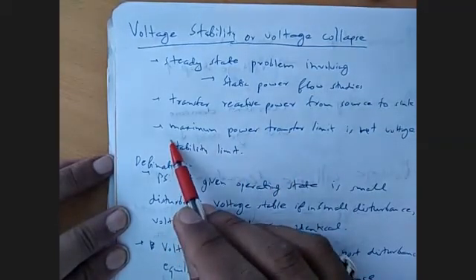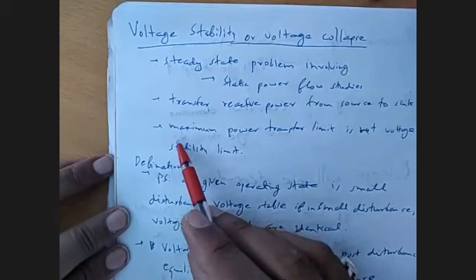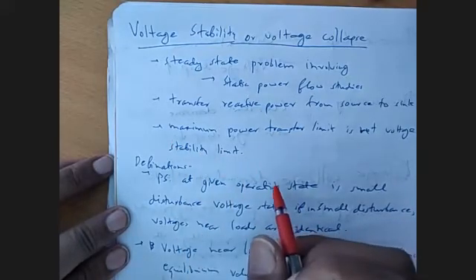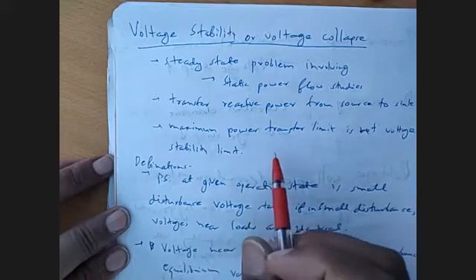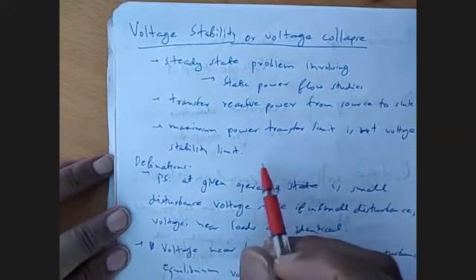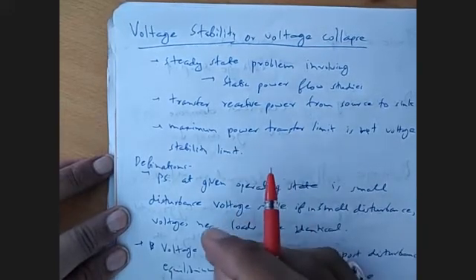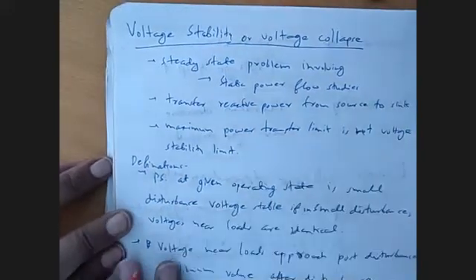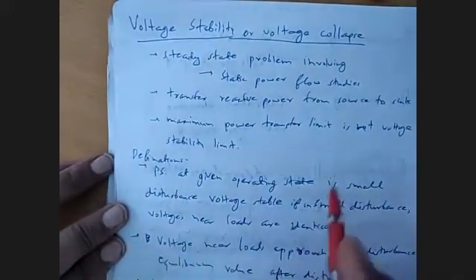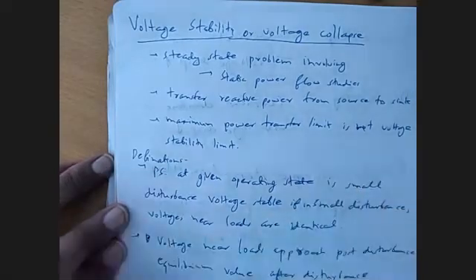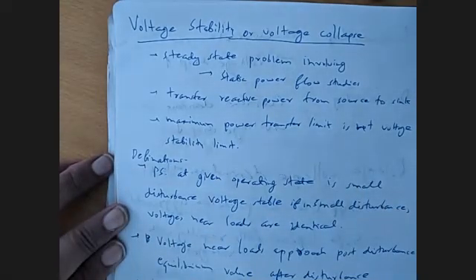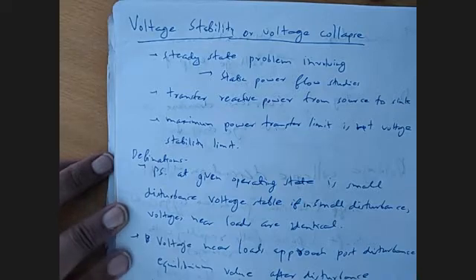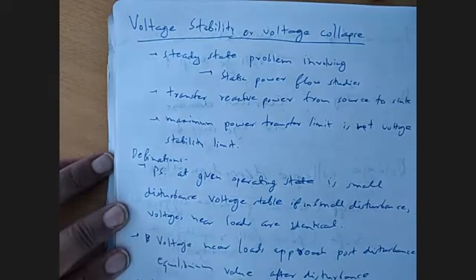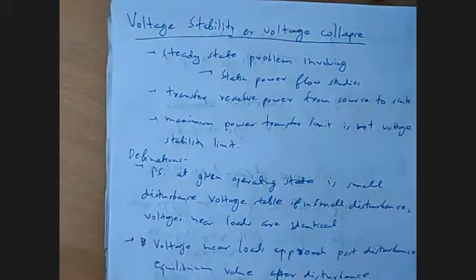Generally, we have heard about a term, maximum power transfer. So the maximum power transfer limit for a power system is not equal to the voltage stability limit of the power system. So they are two different things. In some cases, it may be that the maximum power transfer limit will be equal to the voltage stability limit, but generally they are different terms and they are not indicating the same concept.